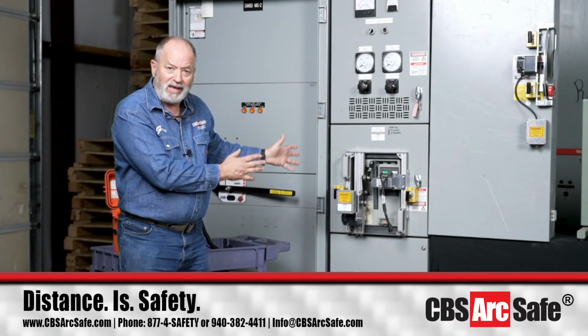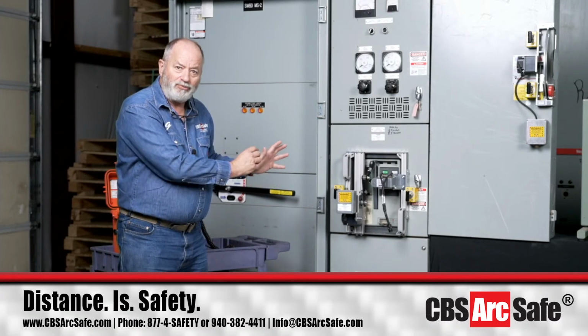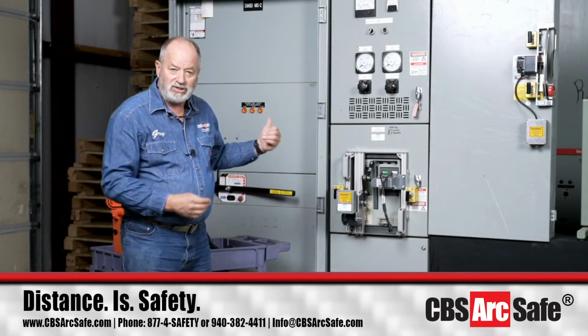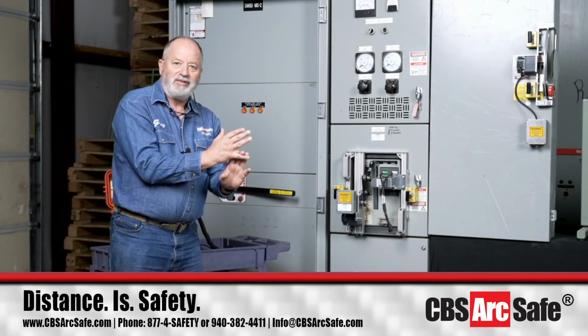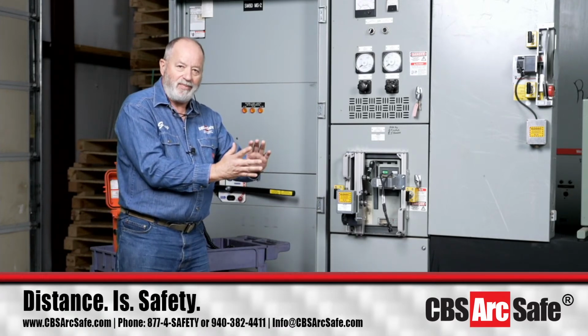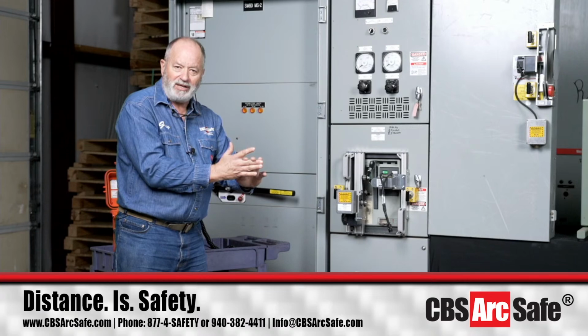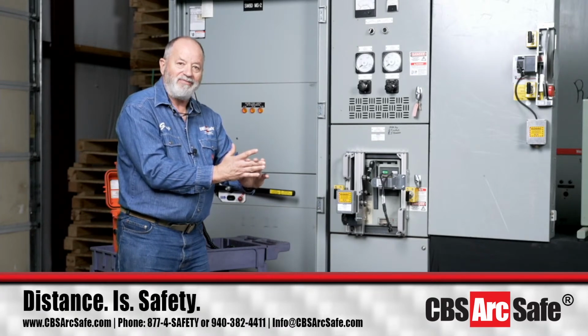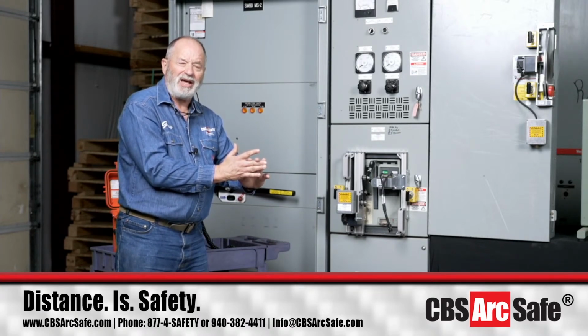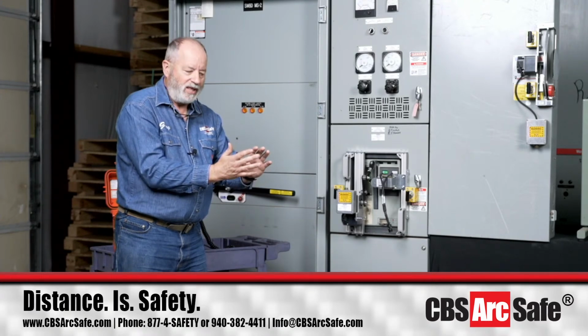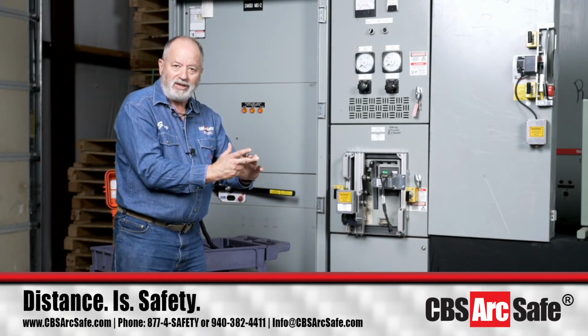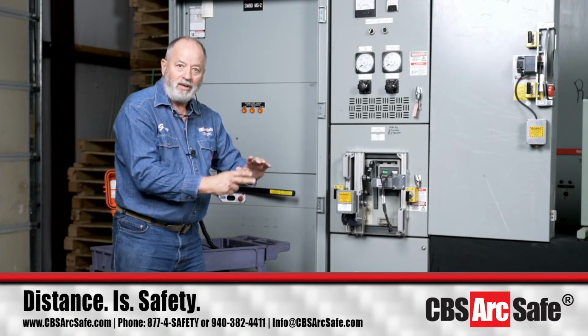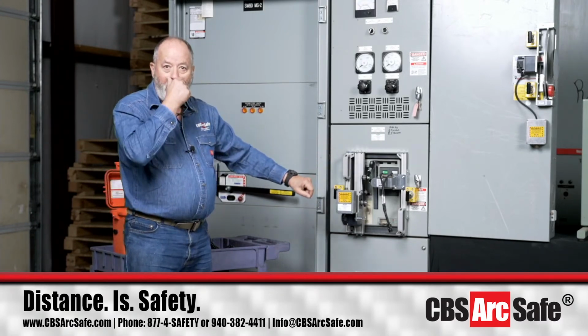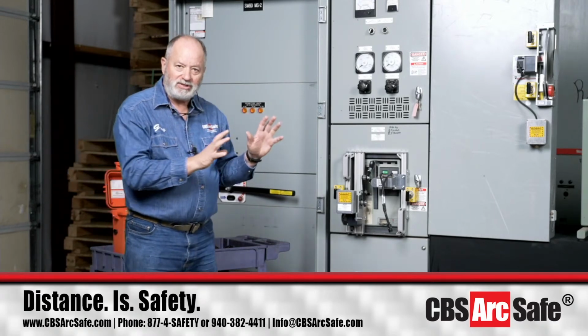So Eaton uses the Magnum DS for several retrofill breakers and changes the label on it. So you can have a Magnum DS, a Magnum SB, a Magnum MWN or Magnum MWI. You can have an IZM breaker. The last two, the MWI, MWN, and the IZM, are all IEC rated breakers, but they're still Magnum DS.